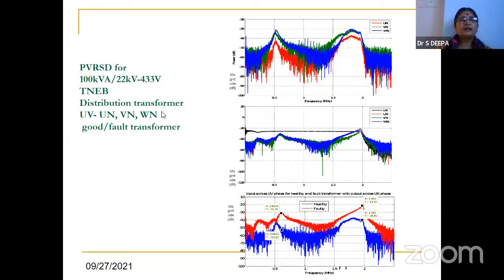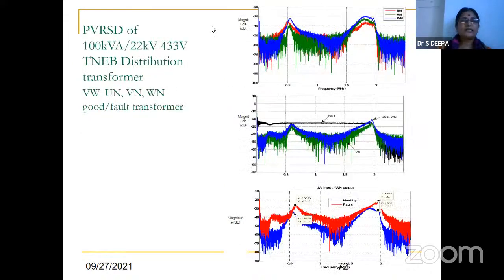Here, peak variation, spectral response for a 100 kVA, 22 kilovolt to 433 volt transformer. So here it is a step-down transformer, a TNEB distribution transformer. It is a good or faulty transformer. So we are comparing what is good and what is bad, and this one is the comparison. Okay, so in the comparison we have more change in the dB. So healthy and the fault: healthy is blue, fault is red. Okay. So in this case, in the same way, the transformer number will be there.